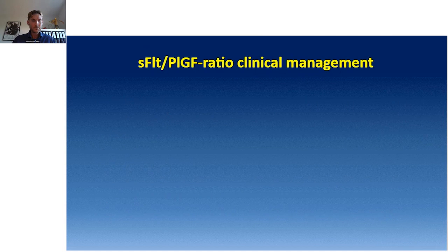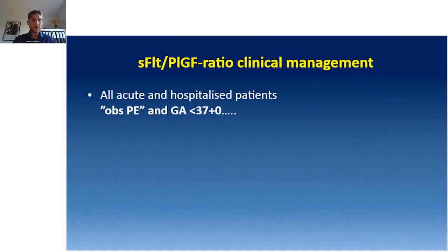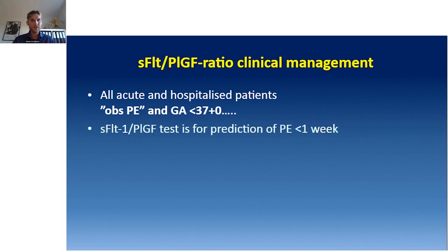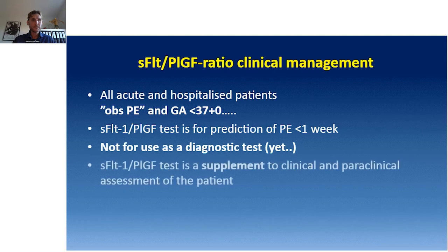For the clinical management, the sFlt-PlGF ratio is indicated for all acute and hospitalized patients with suspected preeclampsia and a gestational age below 37 weeks. The sFlt-PlGF test is for prediction of preeclampsia within 1 week, and it's not for use as a diagnostic test. It is a supplement to clinical and paraclinical assessment of the patient, and it's not for patients already diagnosed with PE.